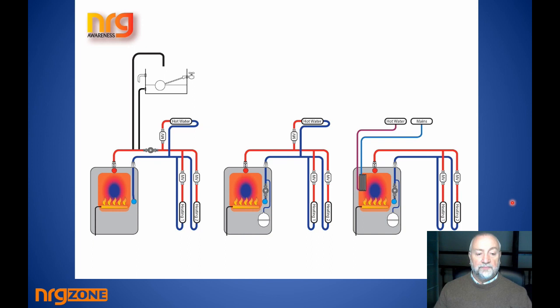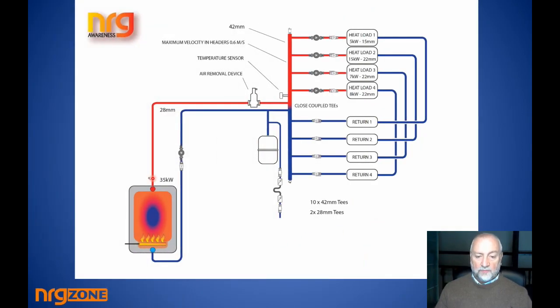So again, we're talking about the effect of the pumps drawing from open systems, from sealed systems, and even where you have a combi boiler, you still have a common area, you still have the pipe that exists delivering heat to the zones for distribution, whatever. So it's fair to say that manufacturers have always recognized that whatever about the pipe sizes leaving the manifold, you might have 22 mil or 28 mil from a boiler, maybe 32 mil, but the fact is that you might be delivering a lot more kilowattage or power than that pipe size would take if it was to be run around the job.